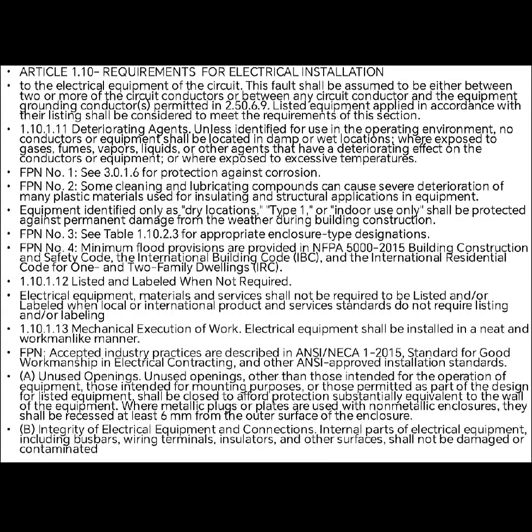Unused openings, other than those intended for the operation of equipment, those intended for mounting purposes, or those permitted as part of the design for listed equipment, shall be closed to afford protection substantially equivalent to the wall of the equipment. Where metallic plugs or plates are used with nonmetallic enclosures, they shall be recessed at least 6 mm from the outer surface of the enclosure. Integrity of electrical equipment and connections: internal parts of electrical equipment, including busbars, wiring terminals, insulators, and other surfaces, shall not be damaged or contaminated.